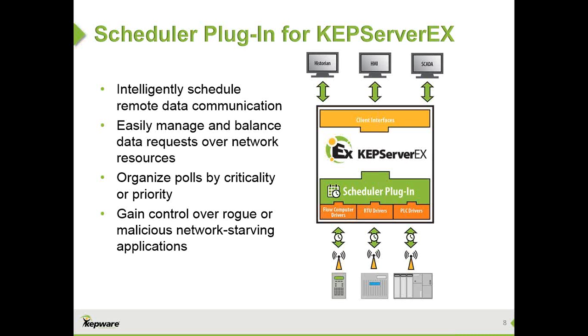And you can define what specific data sets to poll as opposed to the entire tag set or entire item reference set that's defined per device. You can also set priorities for multiple schedules to allow critical data through over non-critical information in case there's an overlap of requests and your network can't handle both at the same time.